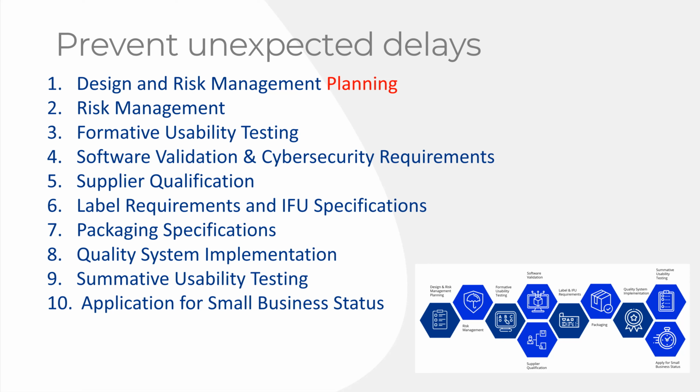and they're actually asking for testing on cybersecurity. So now you have to do vulnerability testing, robustness testing, boundary testing. You have to do penetration testing. They want it to be done by qualified individuals that are independent of your organization, and they want evidence of their qualifications and independence. Now you're going to add another 1,000 pages of documentation to the software section.